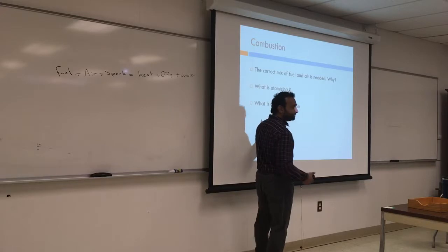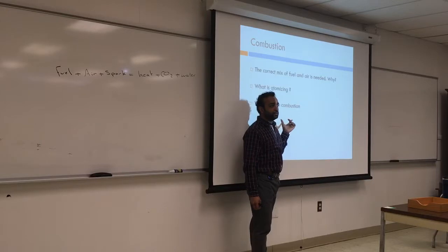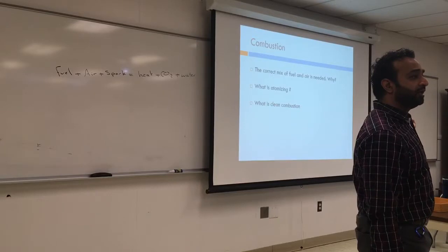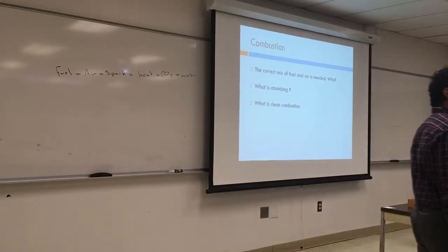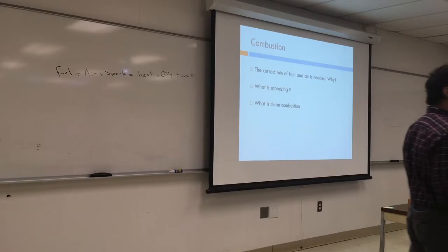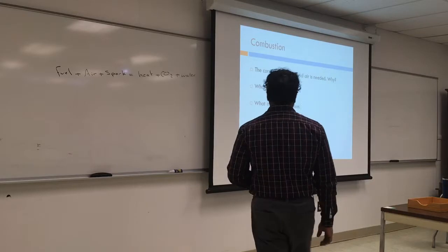So what is clean combustion? It's when we burn the fuel 100% and there is no excess fuel. If you're not burning all the fuel, you're going to have incomplete combustion, and that will lead to having smoke. How do you fix that? You adjust what? The air. So when you had a carburetor, did anybody work with a carburetor ever before? Yeah. So if the car is smoking, on all cars without the catalytic converter, you will go and adjust the air until you stop seeing smoke. We'll do the same thing here in oil burners. If it's smoky, that means you have little air, so you adjust the air using the air vent.